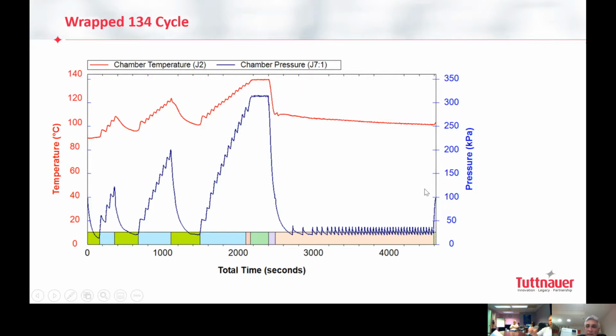drying, which we used to use in your regular machine, the Easy and the MK, by an aeration pump. And by the way, this EKA or this Easy Plus, it is categorized under the class S since it complies with one of the two conditions. It complies with the drying condition. It is drying more than 99%, while the MK, you have to open the door before you start drying. Once you open the door, then this is where we start counting. This is where we test the load. And if it's wet at the moment that we open the door, then it's not complying with the condition. This is the difference between the MK and the EKA or the Easy Plus, which is giving us an effective drying for more than 99% and complying with one of those two conditions that I mentioned at the beginning.